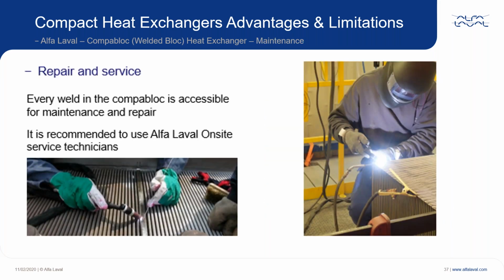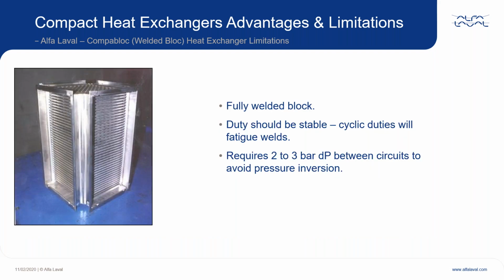In the event of any failures, every single weld on the Compabloc is accessible, so it is possible to repair the welds on them. Although we do recommend you use our welders. As this is a fully welded block, it's quite rigid. So we recommend the duties are stable. Cyclic duties will generally make the plate pack act like an accordion. So you will fatigue the welds and they will break. And also to help avoid this phenomenon, a 2 to 3 bar pressure differential between the circuits is also recommended.